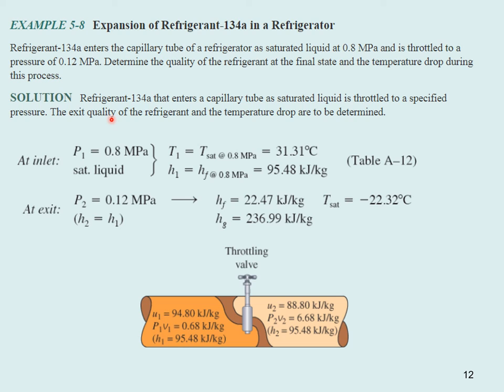Example 5.8: Refrigerant R134a enters a capillary tube of a refrigerator as a saturated liquid at 0.8 megapascals and is throttled to a pressure of 0.12 megapascals. Determine the quality of the refrigerant at the final state and the temperature drop during this process. At the inlet, it's a saturated liquid. P1 is 0.8 megapascals. We can look up the saturation temperature. From table A12, we can find HF at that value. At the exit, it's throttled to 0.12 megapascals. In a throttling situation, H1 equals H2. So H2 equals 95.48.